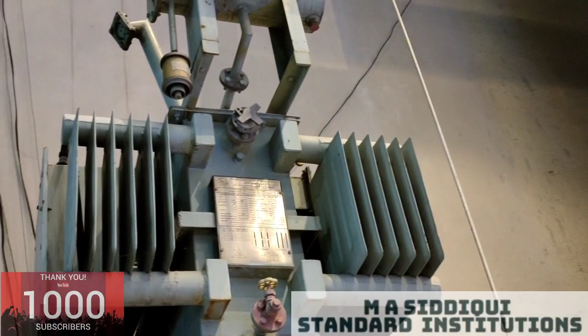The secondary of the CTPT is given to the LBS, load break switch, 11 kV load break switch. Output of the LBS is given to the transformer primary. It's an 11 kV by 440 volt transformer. Output is given to this primary of the transformer. Secondary of the transformer is given to your MDB.